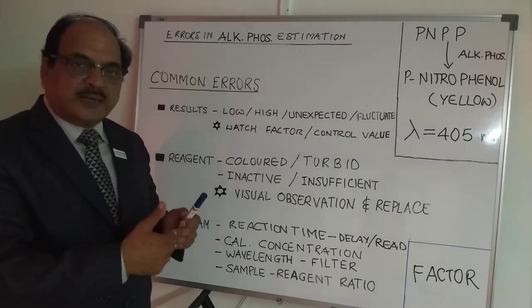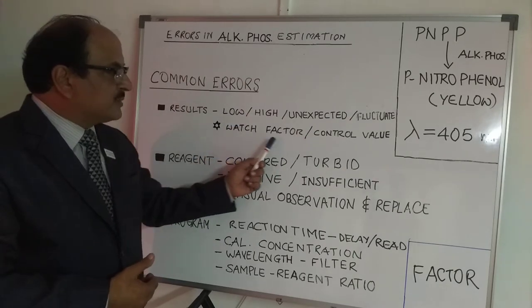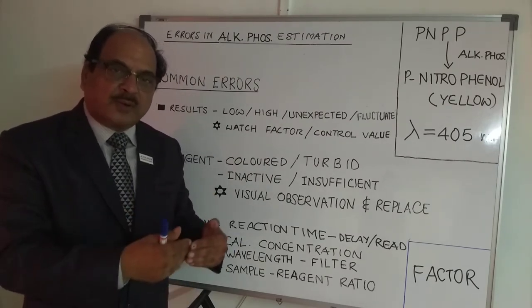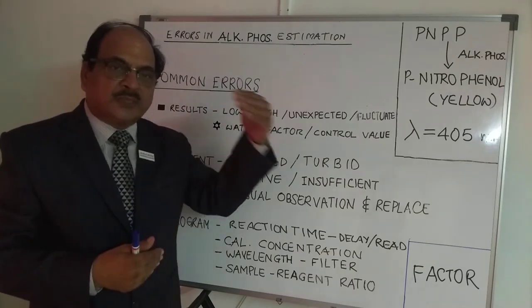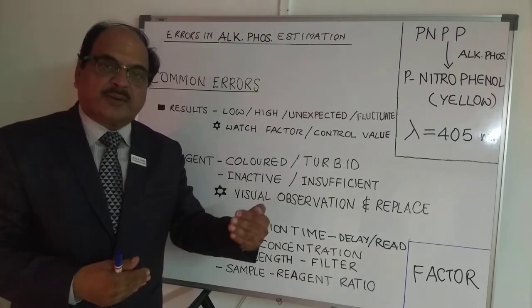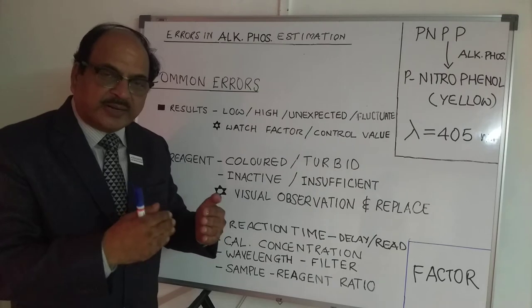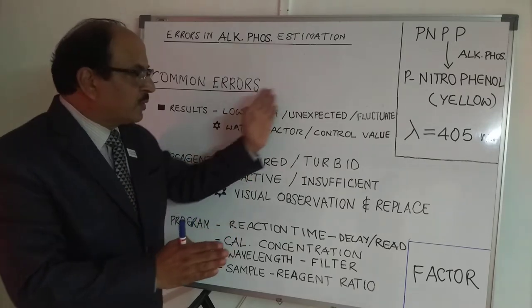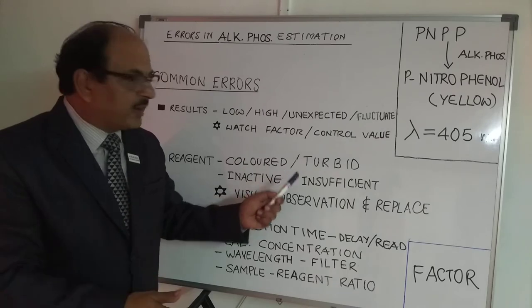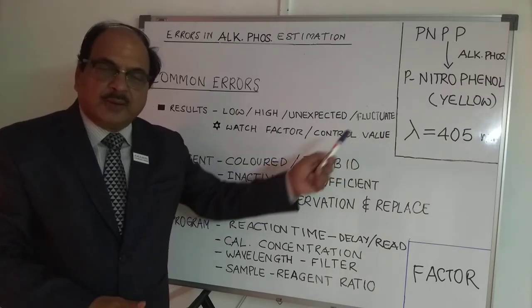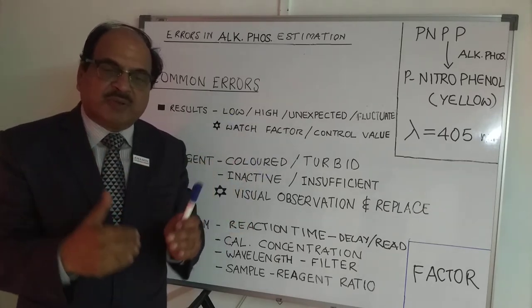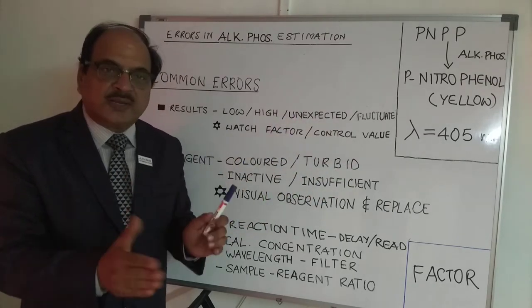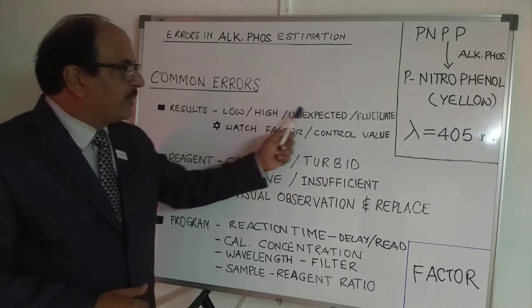It is important to ensure that you do not fall prey to these errors. You must watch your factor when you do the calibration every time. A calibrator when run gets a certain delta absorbance, and the concentration of the calibrator divided by this delta absorbance is the factor. Your success lies in getting your factor close to every day's factor. Further, run a control serum whose value is mentioned lot-specific and method-specific by the manufacturer. When you meet this value at the central value or plus-minus two standard deviations, this guarantees your results are going to be accurate.